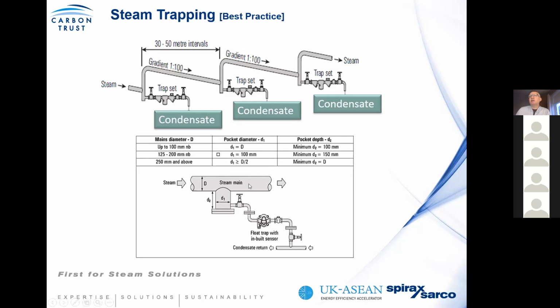When we start looking at the dirt pocket, up to a certain pipe size, so up to a DN100 or 100 millimeter pipe, your dirt pocket should be the same diameter as the distribution pipe. When you go to different pipe sizes, so from a DN125 to 200, your dirt pocket should be at least 100 millimeter. And for a 250 millimeter pipe and above, it should be half the size of your distribution pipe. So having a small DN15 or DN20 tapping means you're not really effectively removing condensate from a distribution system, and you're only having a marginal effect.